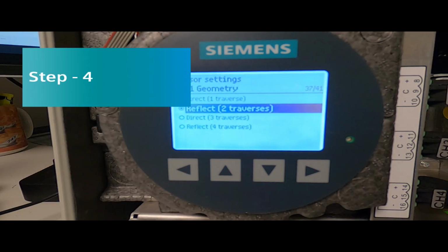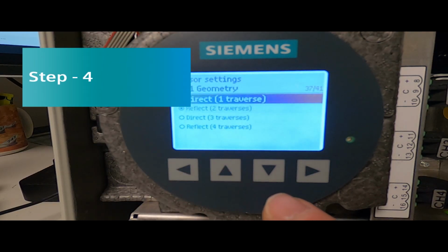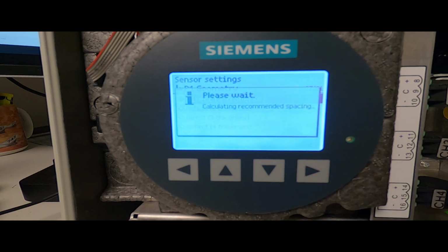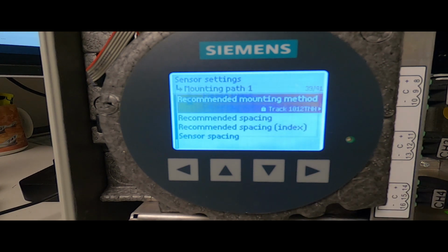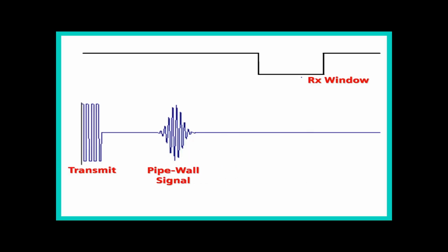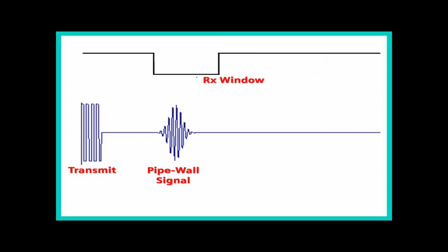Step 4. Change your mounting mode programming to direct. Wait, what? Yes, direct. Remember, the idea here is to get the meter to look for the sonic signal earlier. Direct further reduces the theoretical transit time. Now the signal is expected to arrive even earlier. This will further adjust where the meter will be looking, which should put our RX window in just the right place for the arrival of our pipe wall signal.